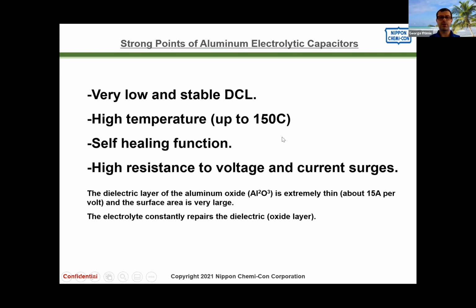You don't have to worry about inrush current, or a sudden voltage decrease or drop, as long as it's not repetitive, especially on the current side. There are limits to this, of course, and if it's a repeating type of event, or outside its normal rating envelope, we'd like to know about it. But for the most part, it's rarely an issue with aluminum electrolytic capacitors.